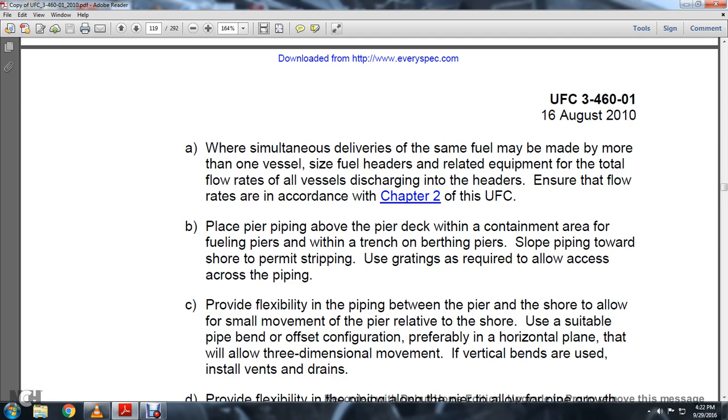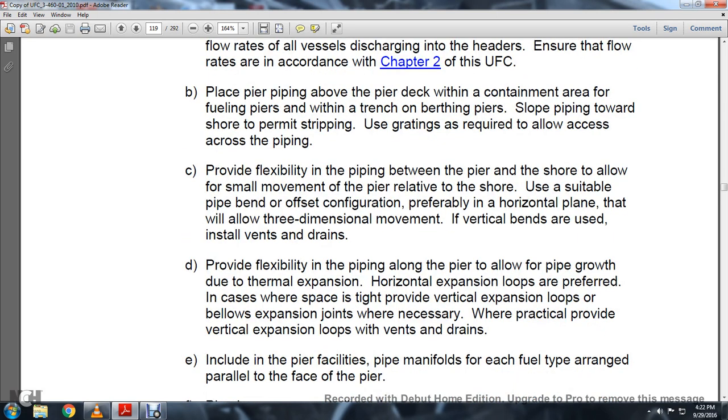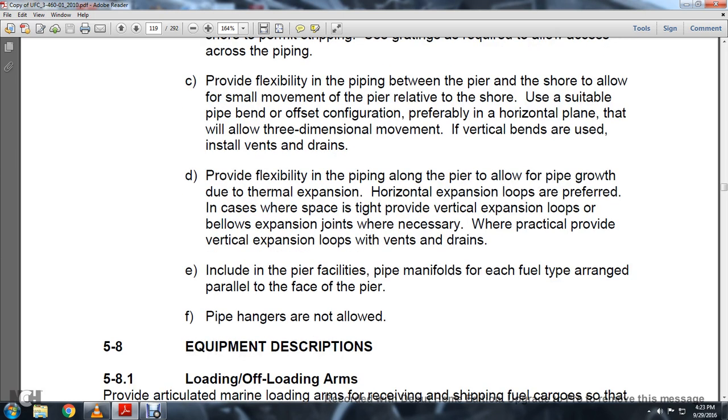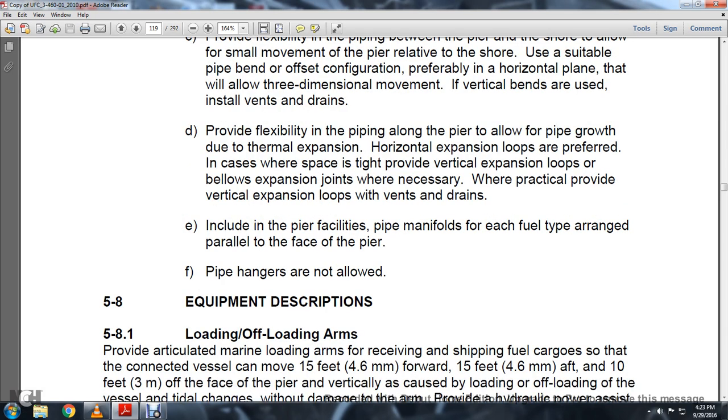At fuel piers which interface with berthing piers, slope piping toward the shore to permit stripping, with grating required to allow access across the piping. Provide flexibility in piping between the pier and the shore to allow small movement of the pier relative to the shore, using suitable offsets in a horizontal plane configuration to allow three-dimensional movement, with vents and drains installed. Provide flexibility in pipe along the pier to accommodate thermal and horizontal expansion using loops where space permits, or vertical expansion loops. Include pier facilities pipe manifolds for each type of fuel, arranged parallel to the face of the pier. Pipe hangers are not allowed.